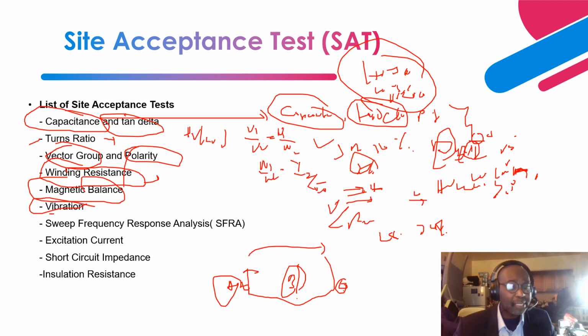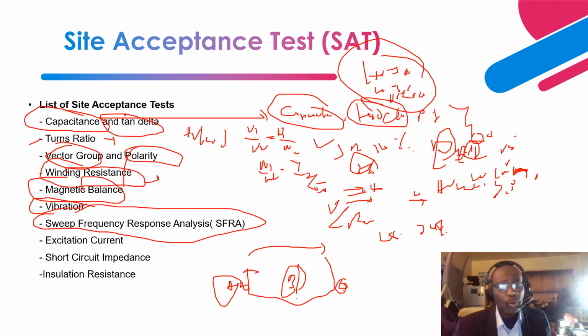Next is sweep frequency response analysis, right? Okay, so sweep frequency response analysis is performed because the transformer is shipped from the factory, right? So you do that testing to make sure there is no internal damage to the transformer, right? If there's any shifting of the active component, that is the core, the winding and the clamping structure, that will manifest itself in the sweep frequency response fingerprint chart. You overlay the current results with the fingerprint results from the factory acceptance test time.